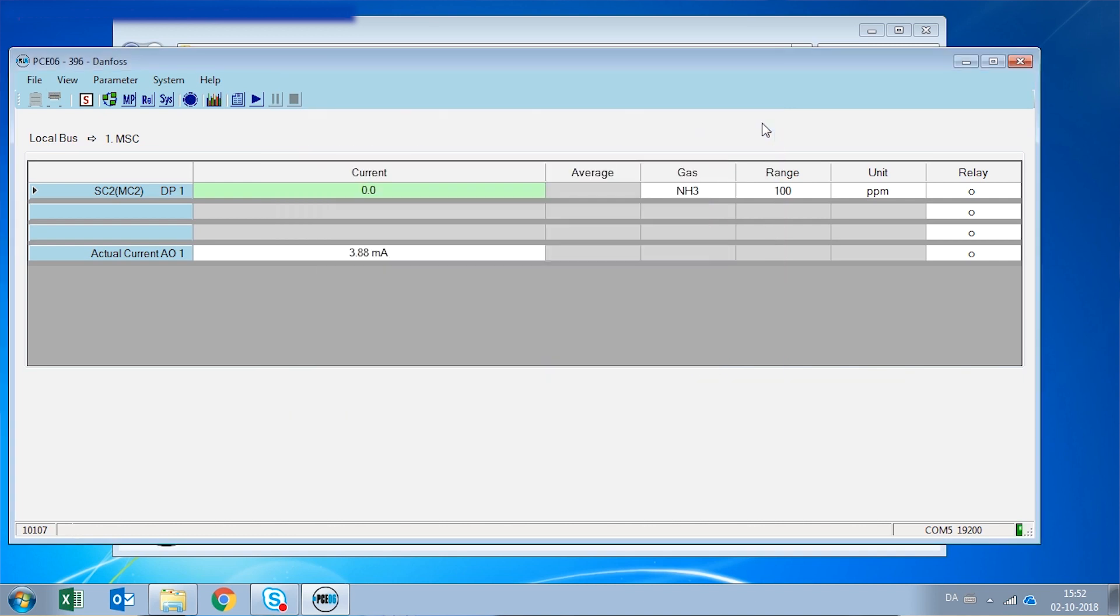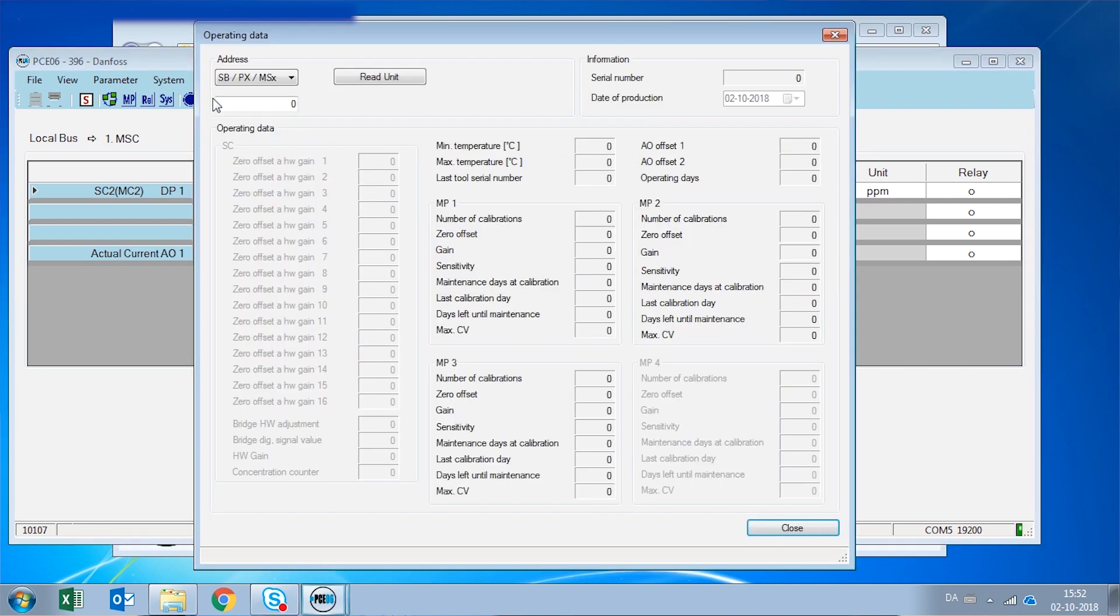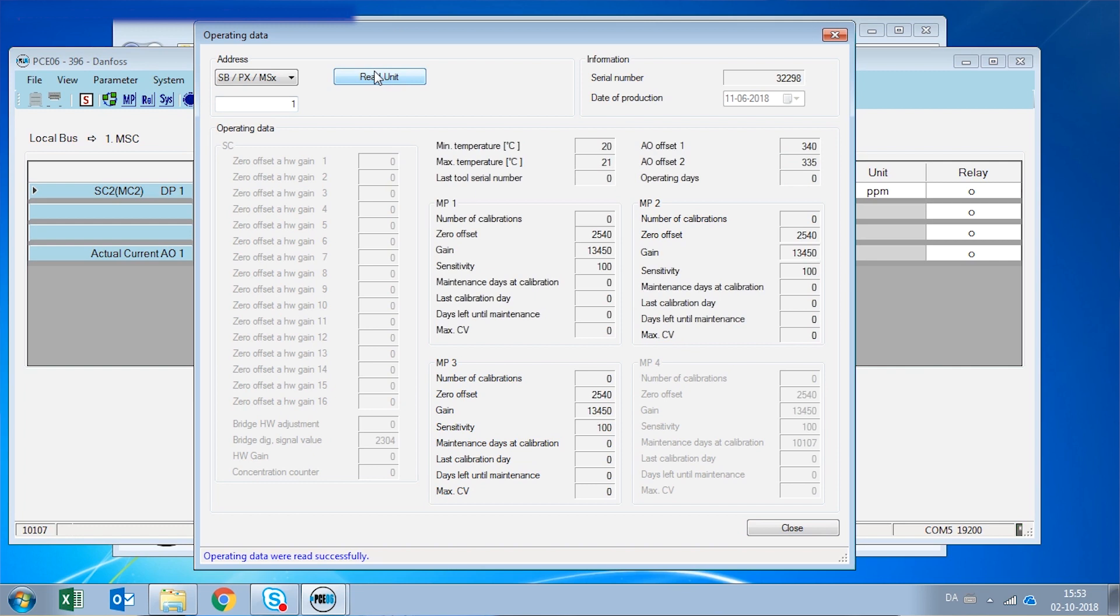The last menu is the operating data. And here we can see all the operating data of our digital gas detector. When we read the unit, we can see the maximum, minimum temperatures that it has seen, how many calibrations it has had, the sensitivity left, and all the operational information on this unit.